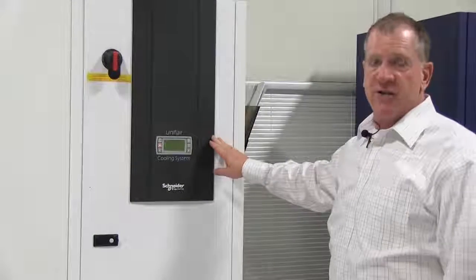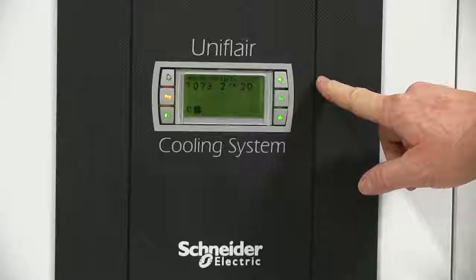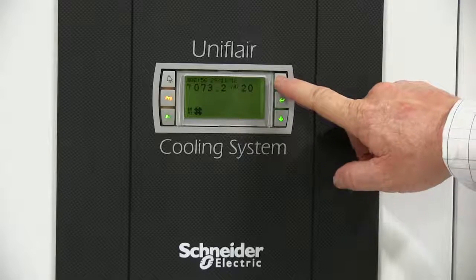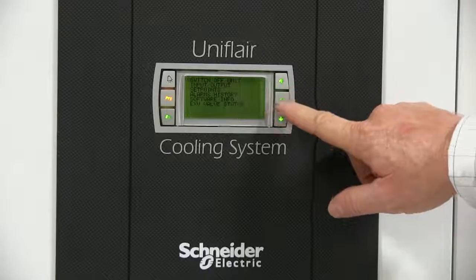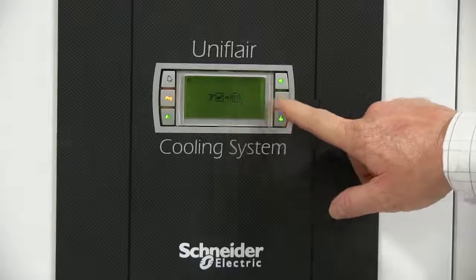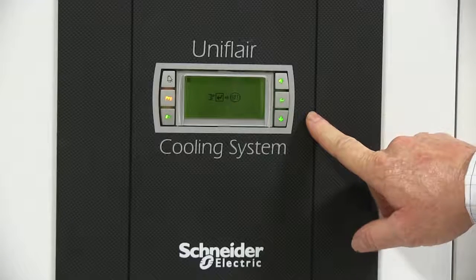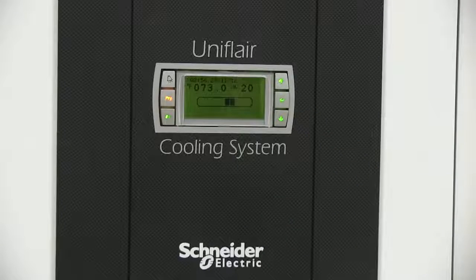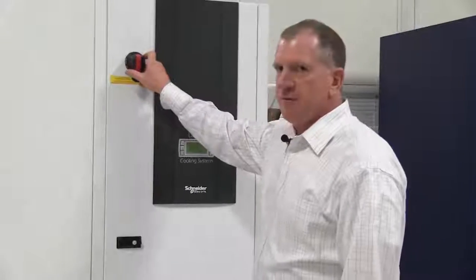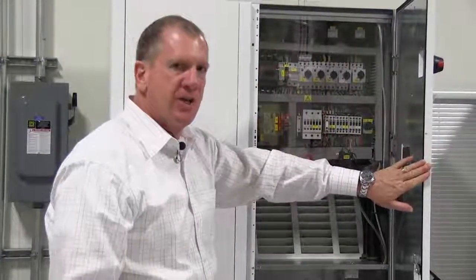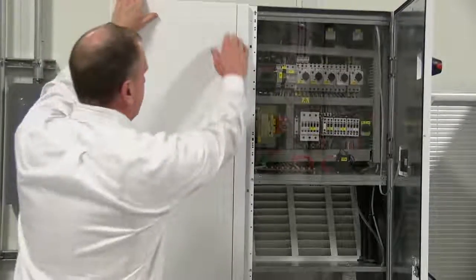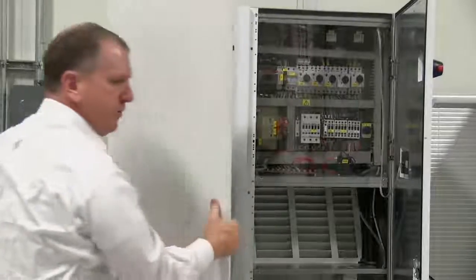At this point, I will power the unit down so that we can access the internal components. I go to the operator display, hit the up arrow, hit enter to switch the unit off, follow the prompt and hit enter again. At this point, the compressors would pump down and the fan will come to a complete stop. Now that the unit has come to a complete stop, we can throw the non-fuse disconnect switch and open the outer panel. The panel for the operator display is hinged. All the other panels on the unit have spring clips. Just by simply pulling, we can remove the unit panel.